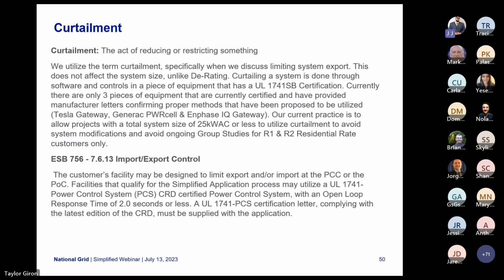So our current practice is to allow projects with a total system size of 25 kW AC or less single phase to utilize curtailment to avoid any system modifications for that proposed project and avoid ongoing group studies. And again, that's for R1 and R2 residential rate customers. And right here is the excerpt out of the ESB 756 7.6.13 that covers the import and export control for power control systems. National Grid is going to be looking to expand this section to allow what we just covered up to 25 kW AC single phase.